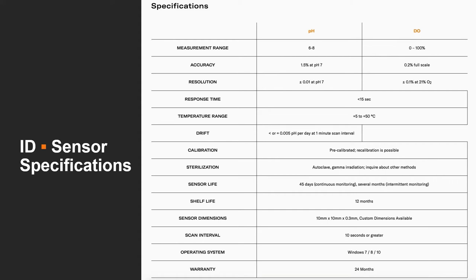The biggest advantage to these sensors is the versatility and the size. Sensors can be anywhere from one centimeter square and are 0.3 millimeters tall — just a couple of pieces of paper stacked on top of each other — and get down to three millimeters in diameter. You can imagine a three millimeter diameter sensor with a 0.3 millimeter height being placed into your microfluidics device. They're also meant to be single use — you use them once, throw them away — so there's no sterilization burden and no risk of contamination. And they're inexpensive, so the cost is not prohibitive for running multiple experiments.